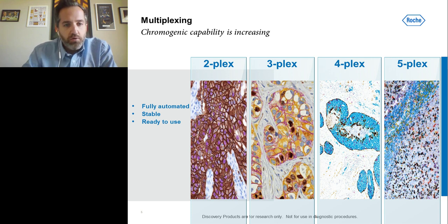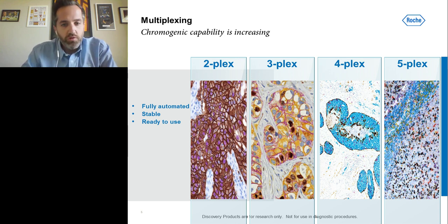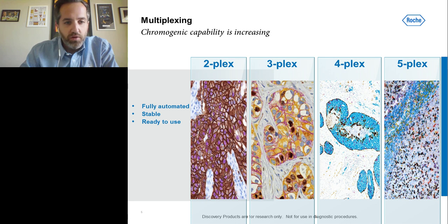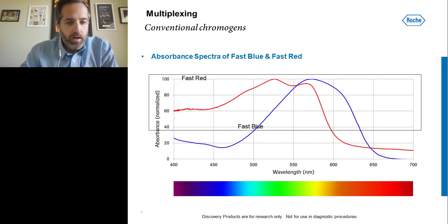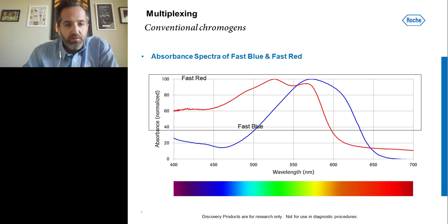Chromogenic multiplexing has really expanded over the past two to three years with the introduction of these new chromogens and the expansion of automation within Roche Tissue Diagnostics. We're now seeing five or six different markers on the same slide. This is all down to how the new chromogens work. Conventional chromogens such as fast red and fast blue have a very broad absorbance spectra, making them very difficult to deconvolute — if they overlap, it's very difficult to see different colors emerging.